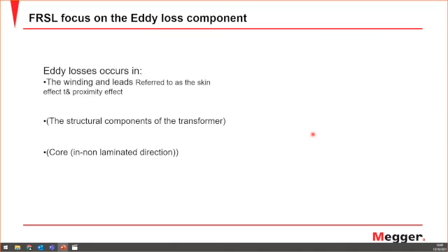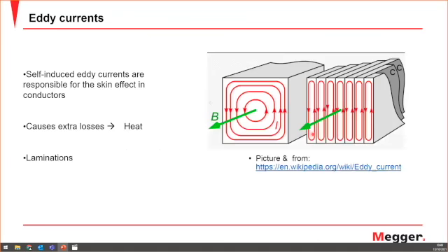the skin effect. But before that, regarding the self-inductance eddy current, we have designed our transformer to have laminations which can reduce the eddy current, and we are insulating between each plate here. So we have less and less eddy current and better flux moving, but if we had it all in one piece, it would have a huge current and an increase in the reluctance. For that purpose, we design our transformer today this way, which will reduce the eddy current. But if the transformer starts losing this little insulation, this may generate more eddy current in this part, which will add heat to the power transformer. And the way to detect it is by doing this FRSL. When you measure at higher frequency, this will appear more clear and more obvious for our testing.